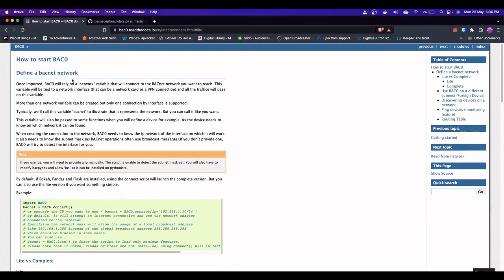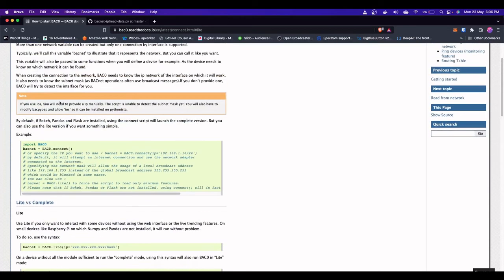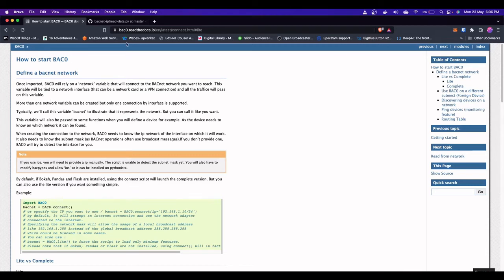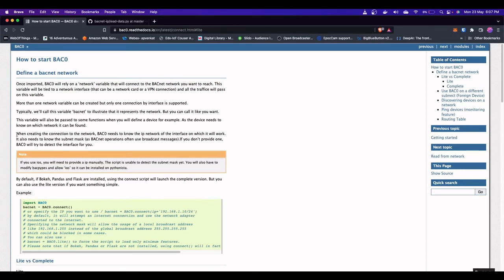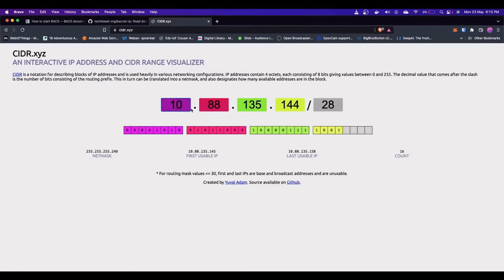The Python module we'll use is BAC0. Search for it on Google and you'll reach the documentation at bac0.readthedocs.io. The docs are clear: when creating a connection, BAC0 needs to know the IP network of the interface it will use. My local subnet is 192.168.18.x — a /24 subnet giving access to up to 254 IPs. It also needs the subnet mask. You can verify your subnet and usable IP range at cidr.xyz.